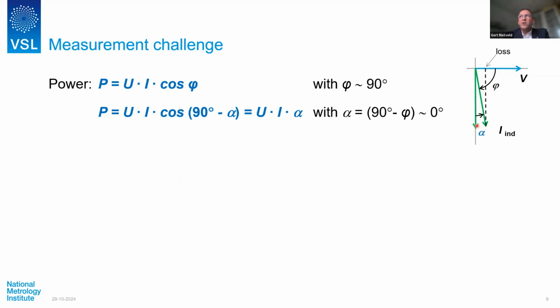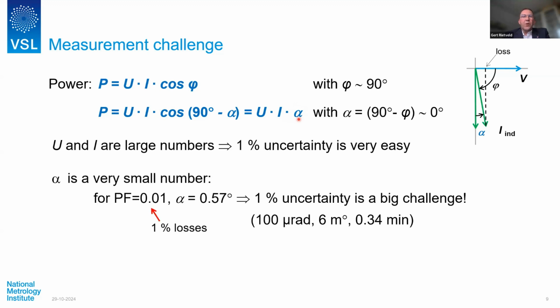So phi is roughly 90 degrees, and you can phrase it also as 90 degrees minus alpha. And if I then do this, the cosine of 90 degrees minus alpha can be approximated with roughly alpha, the phase angle. And this is the key formula for power transformer loss measurements. Because voltage and current, these are large numbers, and to measure these with 1% accuracy is not really that difficult.